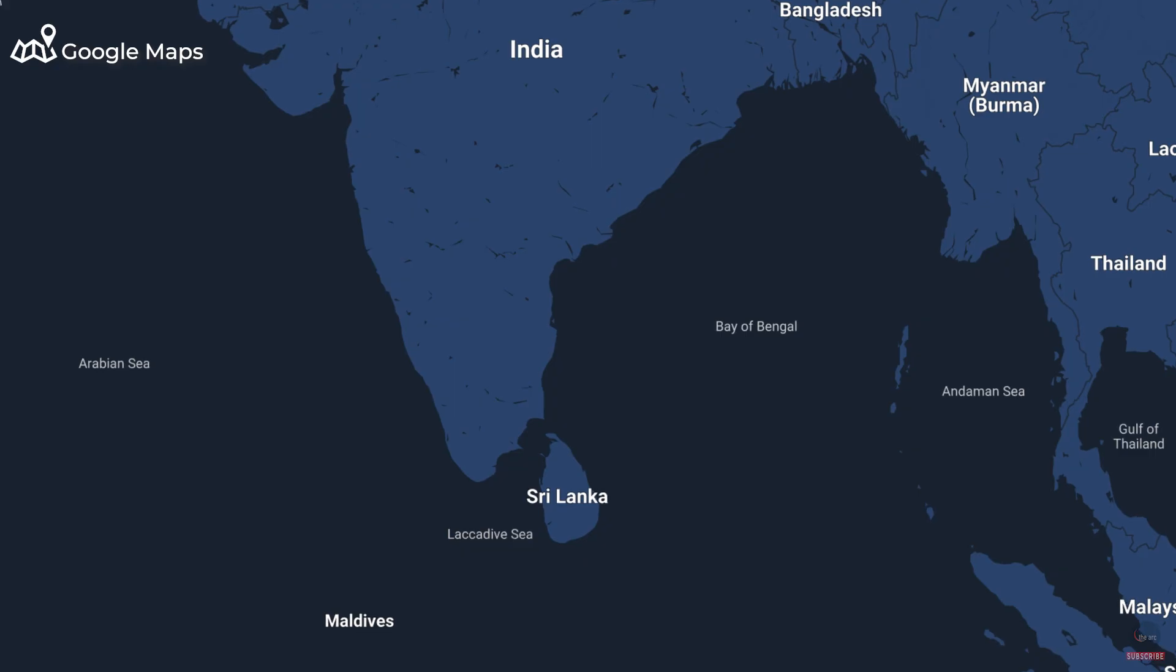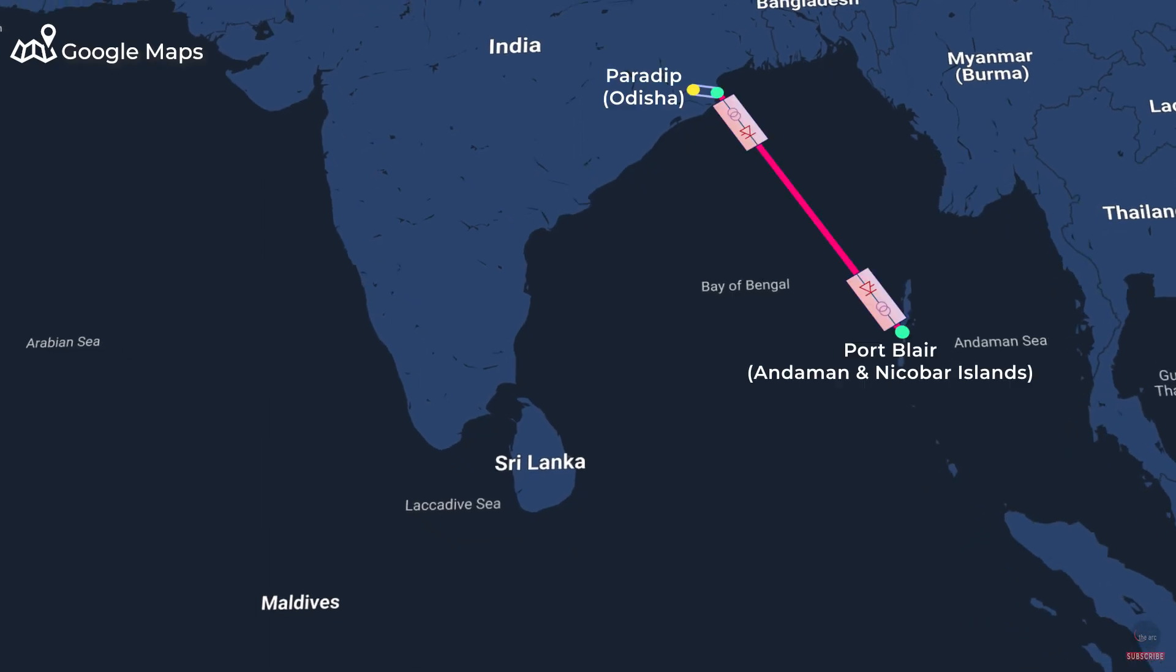The project aims to connect Andaman and Nicobar Islands with the mainland of the country through HVDC undersea power cables. It will be a plus minus 320 kV, 250 MW HVDC voltage source converter interconnection between Paradip in Odisha and Port Blair, the capital city of Andaman and Nicobar Islands on southern Andaman Island. The total length of the undersea cable would be 1,150 km.